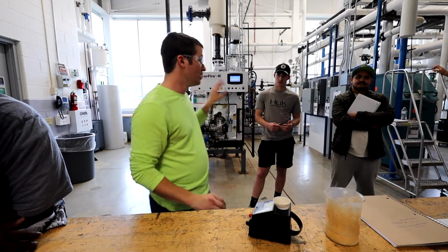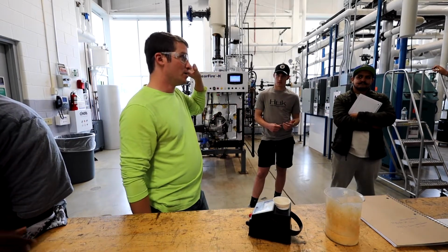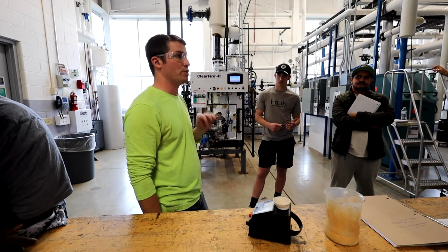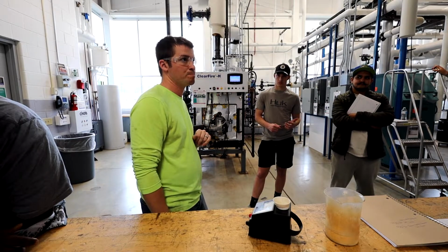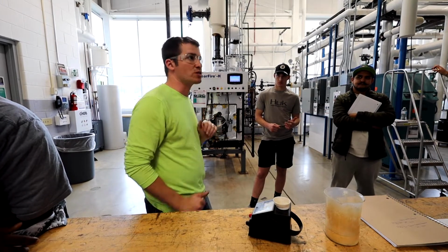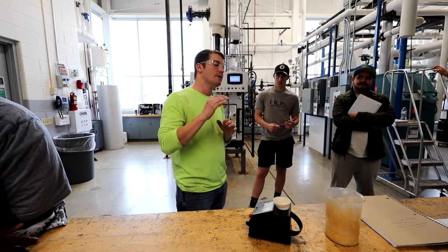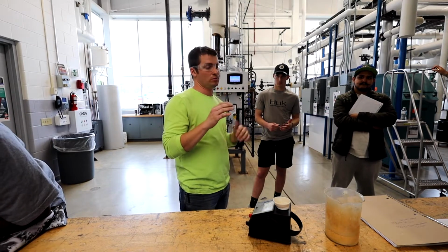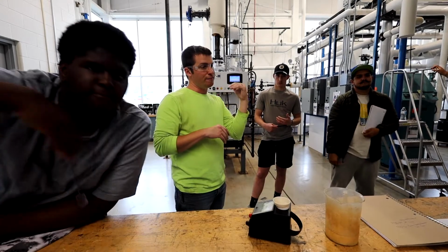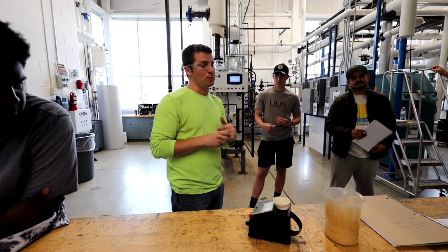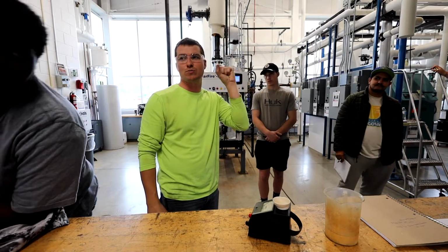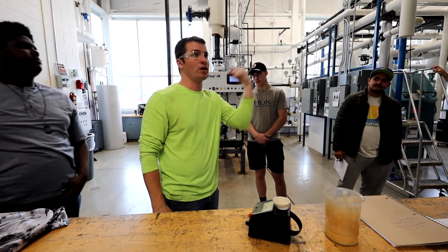So a typical Lake Michigan soft water boiler, I would say we probably are going to run in the neighborhood of 3,000 to 4,000 on the conductivity. If you had RO, maybe we could push it to 5,000, 6,000, but that's kind of really the upper limit that you want to go. The higher you go, yep, the more cycles. So running 50 cycles is a lot better than 10 cycles, but running 100 cycles compared to 50, the payback is so small, it's not worth the risk of running that high, all right?